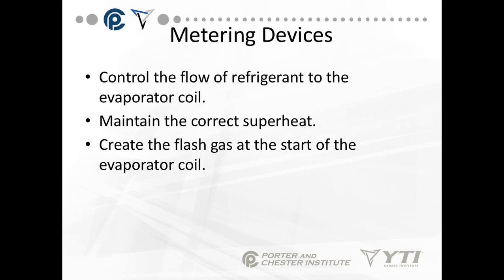The metering device has basically one purpose, and that's to control the flow of refrigerant to the evaporator coil. It's supposed to maintain the correct superheat, and it creates the flash gas at the start of the evaporator coil. It's a point of pressure drop. We come into the metering device with high-pressure liquid. We leave with low-pressure liquid mixed with some vapor, which is called flash gas. Think of it as the spray nozzle on a garden hose.